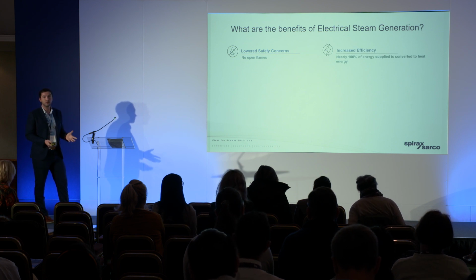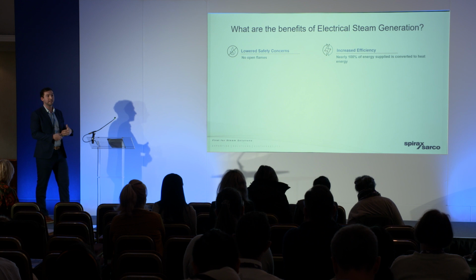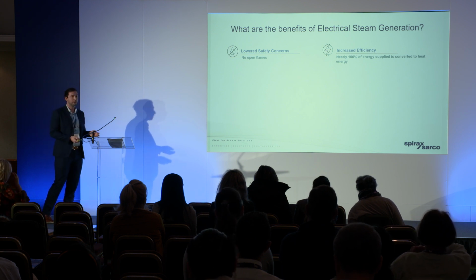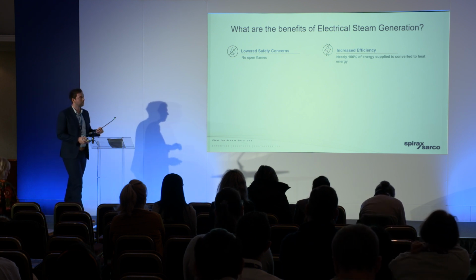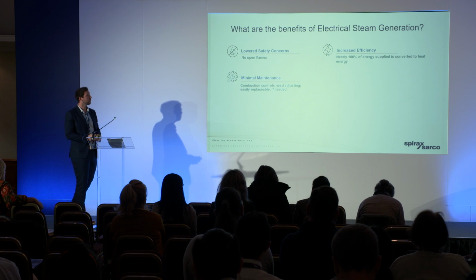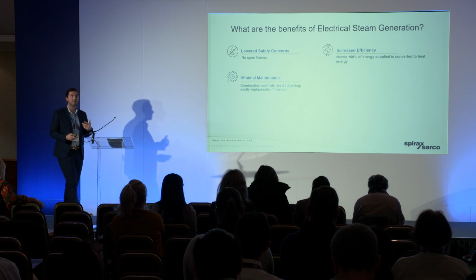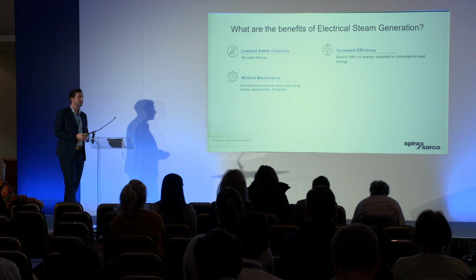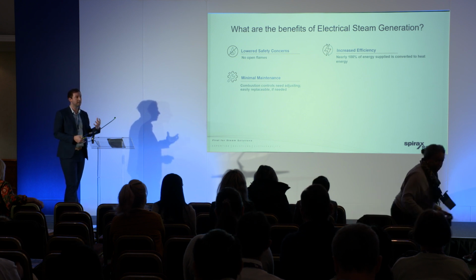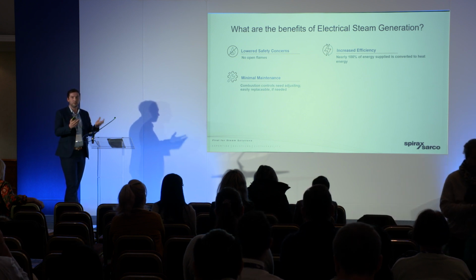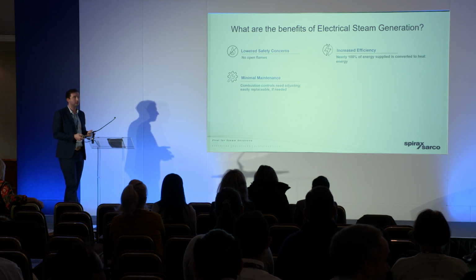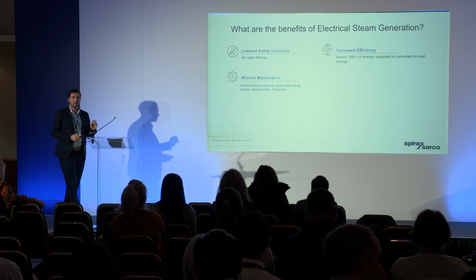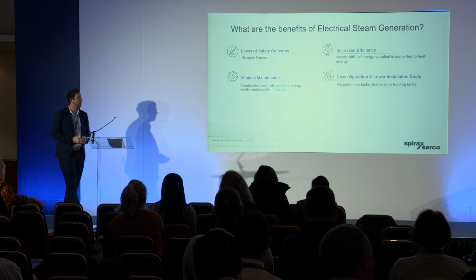Increased efficiency. We don't have any losses through the stack. There's no exhaust as such from the boiler. And we have really precise control, which I'll cover in a second. We don't have the same kind of maintenance requirements from managing a burner, from cleaning tubes, from the scale up of the heat transfer area inside the boiler, so we can reduce the costs of that slightly too.